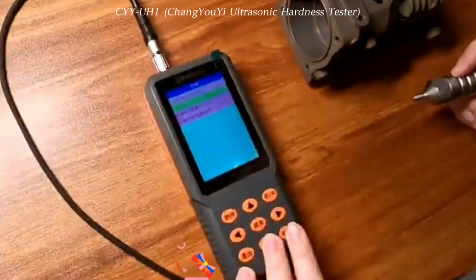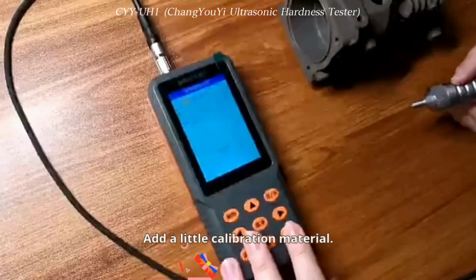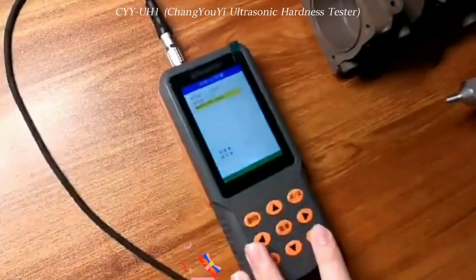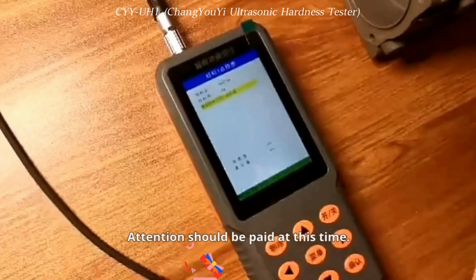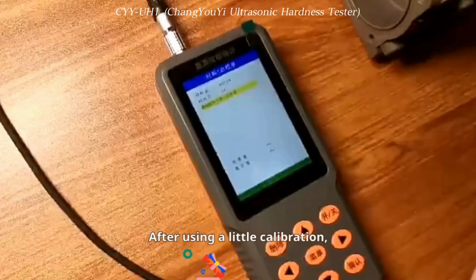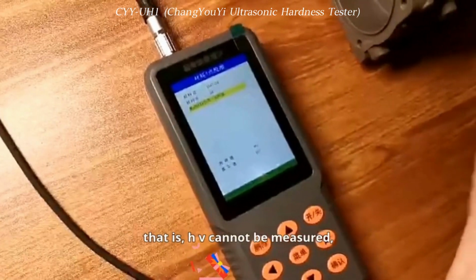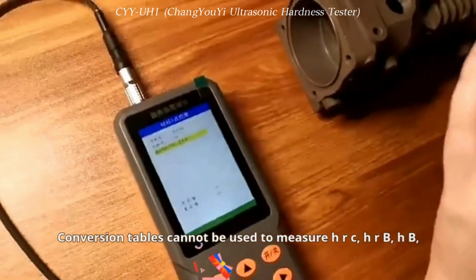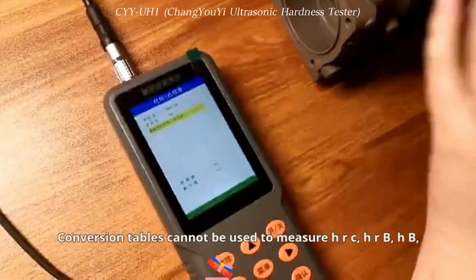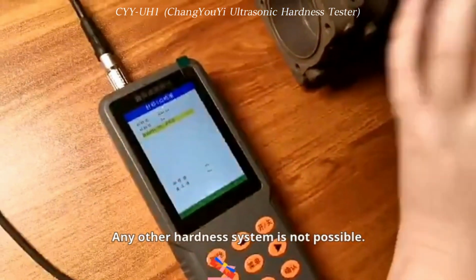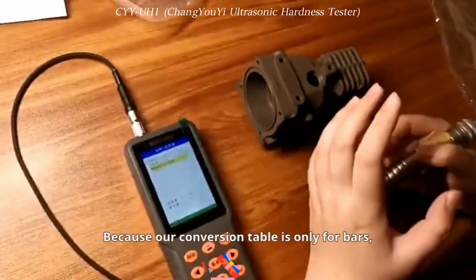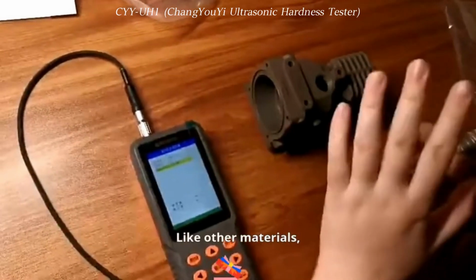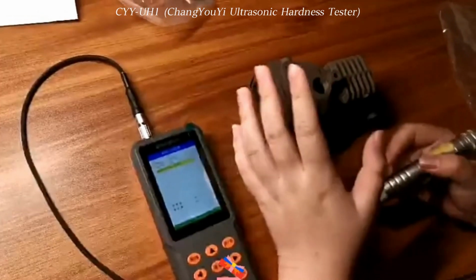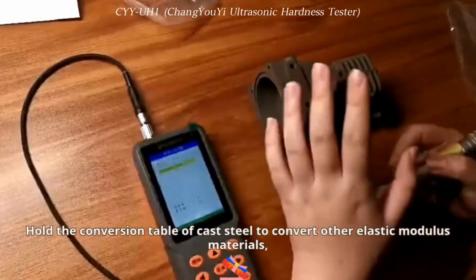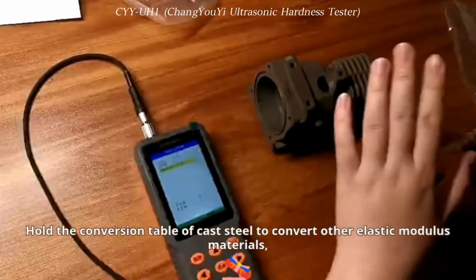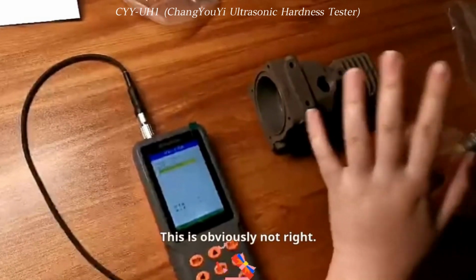Menu, materials, add a single-point calibration material. Attention should be paid at this time. After using single-point calibration, it can only be measured as HV, and the conversion tables cannot be used to measure HRC, HRB, HB, or any other hardness system, because our conversion table is only for steel. Like other materials, after you do a single-point calibration, you are equivalent to using the conversion table of cast steel to convert materials with a different elastic modulus. This is obviously not right.